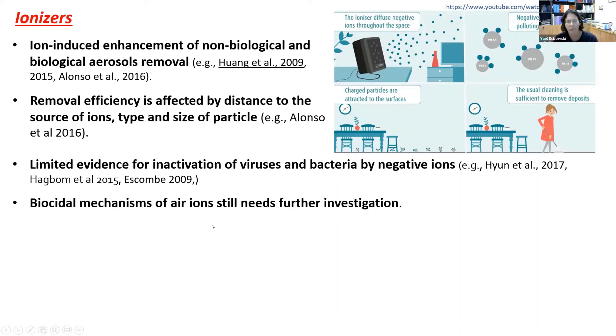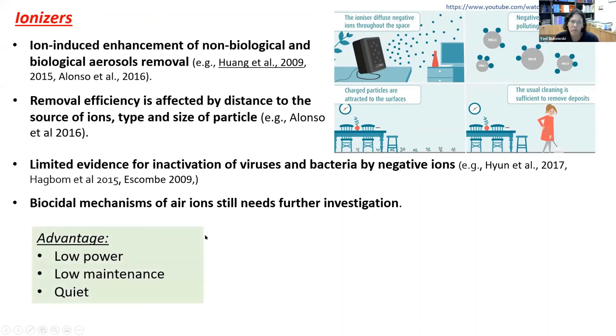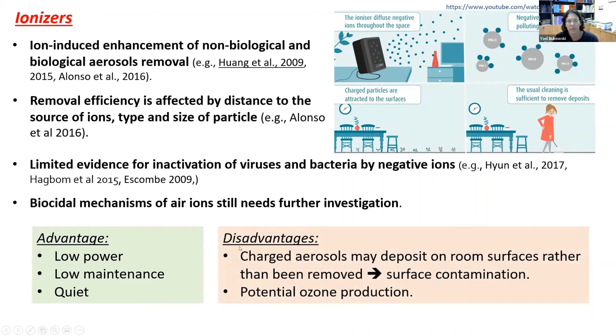There are still uncertainties in this field — the mechanism of bioaerosol inactivation is not fully understood, so there is much space for research. Overall, this technology requires low power demand, low maintenance, and is relatively quiet. However, the disadvantage is that we are removing aerosols onto available surfaces, so without also cleaning those surfaces, we can transfer the problem from airborne to surface contamination. Additionally, because of the high electrical field involved, there is potential ozone production.